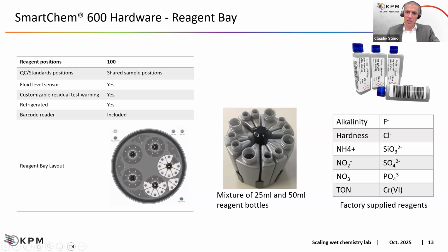And on this slide, we can also see that we are providing ready to use reagents for a really huge list of parameters. Alkalinity, hardness, ammonia, NO2, NO3, TON, fluoride, chloride, silica, sulfate, chromium. And now we are also going to add calcium, magnesium, because one of the trends is also to run calcium and magnesium to be able to determine calcium hardness and magnesium hardness.